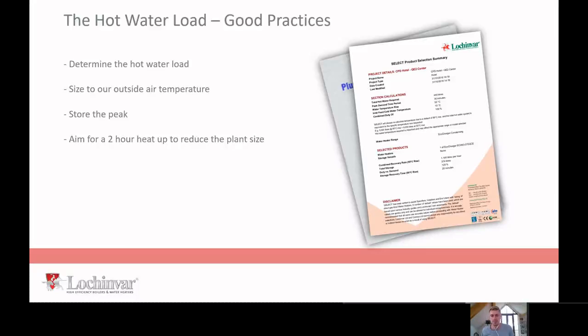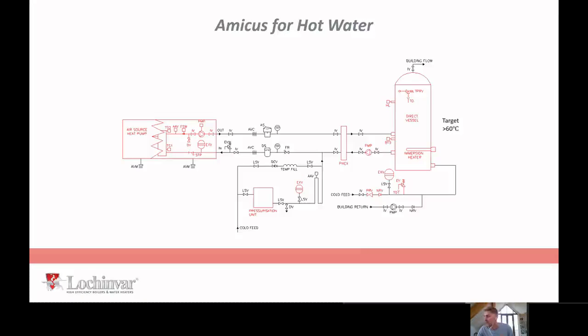So when you're working with an air source heat pump, at your design condition, when you're looking at hot water, you're looking for a 2-hour heat up time typically, unless it's healthcare and we're insistent that it's got to be a 1-hour heat up time, in which case that's perfectly acceptable, but you are going to lose some efficiency on the system, and you're going to increase the cost of the initial capex. Okay, so a hot water application or dirty heating system application.